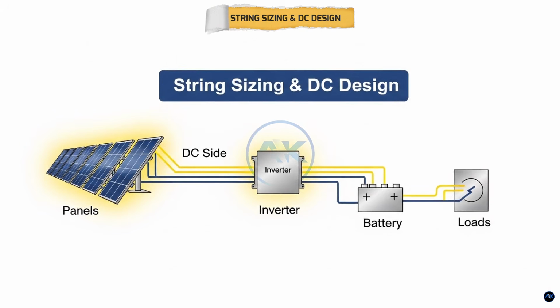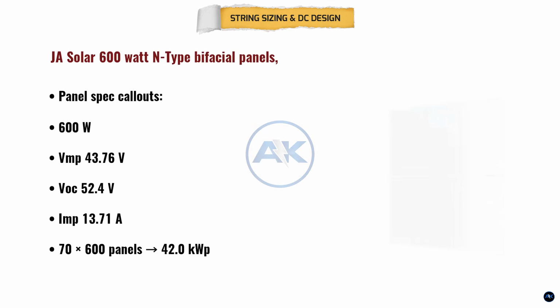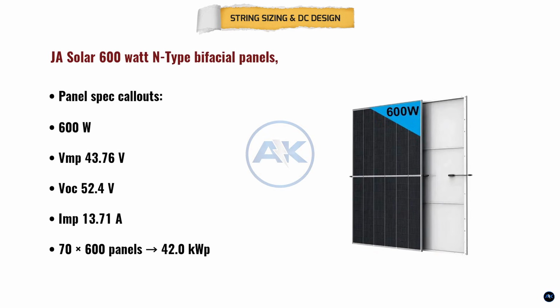the solar panels. Before installing the solar panels, we must first finalize the string sizing and DC electrical design. This step ensures the system operates safely, efficiently, and within the inverter's voltage and current limits. This system uses 70 JA Solar 600-watt N-type bifacial panels, giving a total solar capacity of 42 kilowatts. Each panel has a maximum power voltage of 43.76 volts and an open circuit voltage of 52.4 volts.